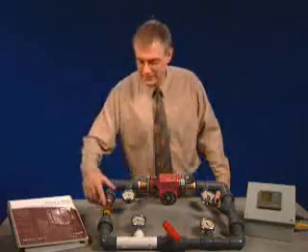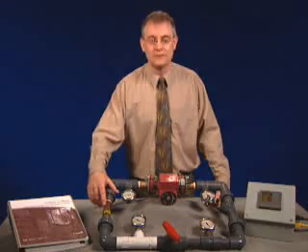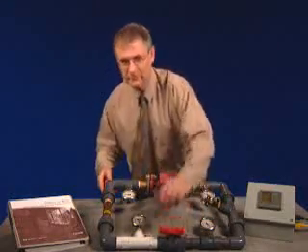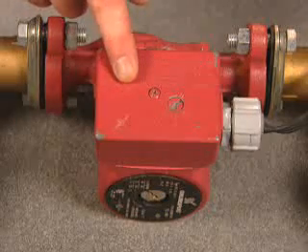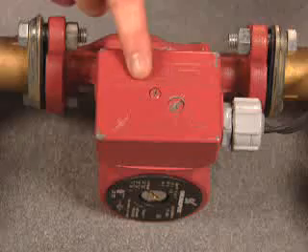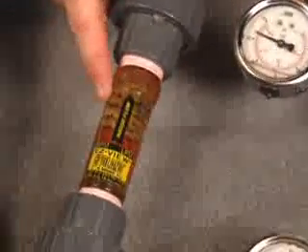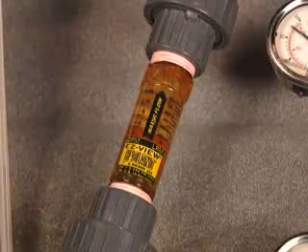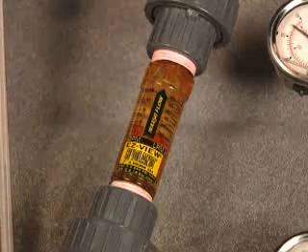We now have 3 gallons per minute, which is what we need, but there's another way to achieve this flow, and that's to slow the pump. But first, let's open the valve. The system is back to 73 watts. This pump has 3 speeds, so I'm going to go from full speed to half speed. We're now at 4 gallons per minute, still more than we need. Now we're at the lowest speed, and the pump is circulating 3 gallons per minute. That's our desired flow rate.